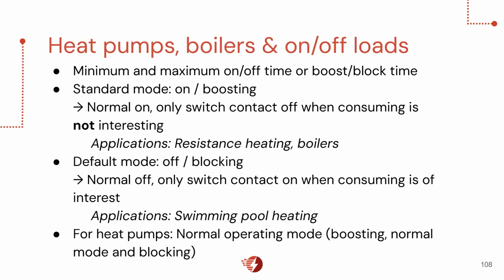For heat pumps, it's a little different. We have some standard modes called boosting, blocking, or normal operating mode. In boosting mode, we only switch the contact off if consuming is not interesting. For blocking, it's the other way around: we only switch the contact on when consuming is of interest. For heat pumps, most people like to leave them in normal operating mode.